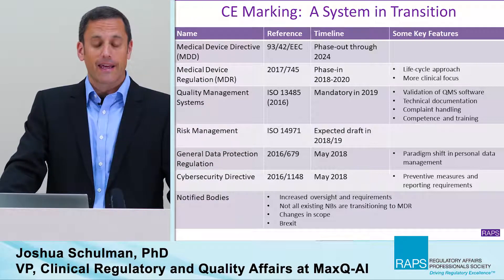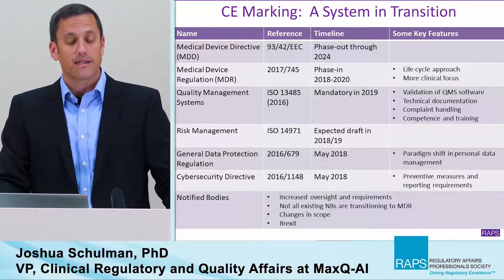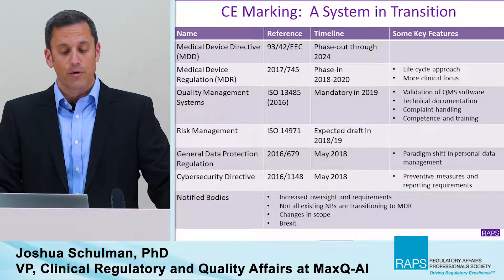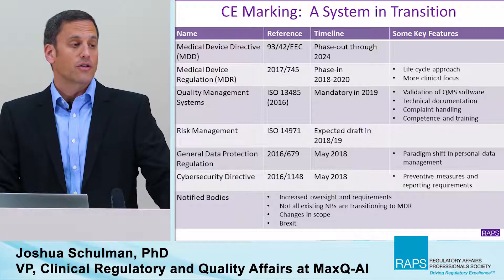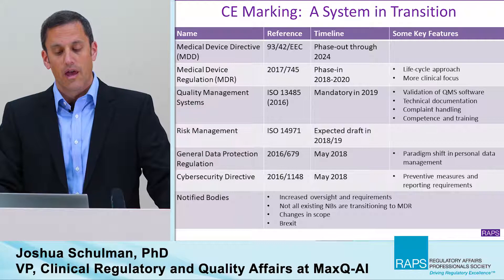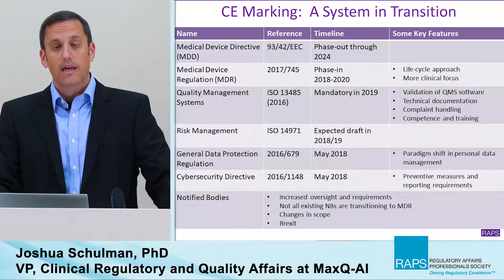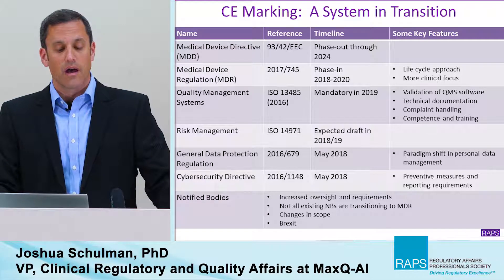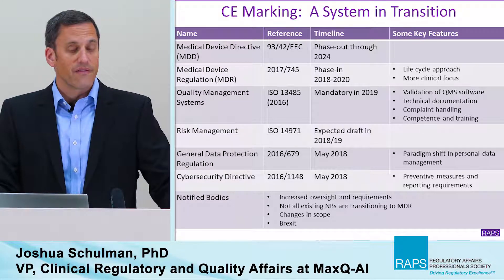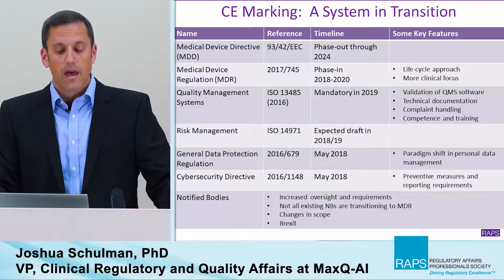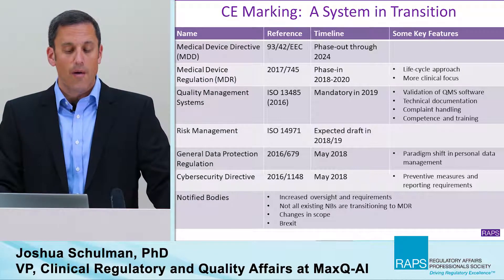At the same time, there are a number of critical standards that underlie quality systems for device development. ISO 13485 is probably the most important of these, and it is also undergoing a change with mandatory transition into the 2016 version by February of 2019. Some of the critical changes in the 2016 version of ISO 13485 include a requirement to validate QMS software, a new structure for technical documentation, new requirements around complaint handling, and new requirements around competence and training of staff.